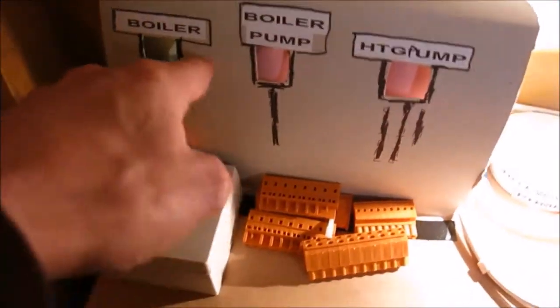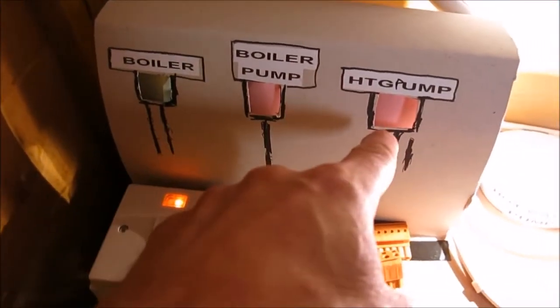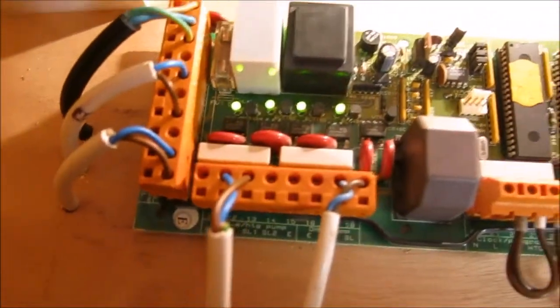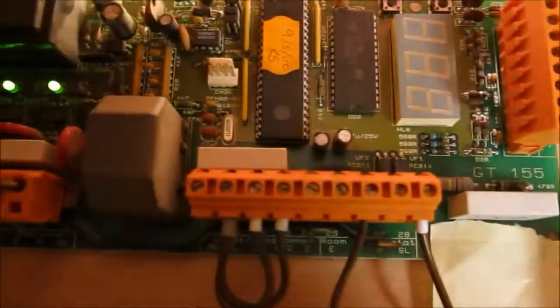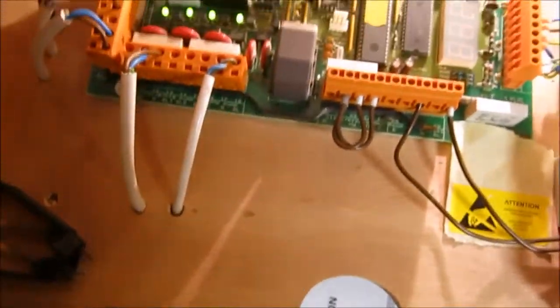I'll show you that in a minute. More importantly, if those LEDs are on, the boiler pump and central heating pump should all be on as well, and clearly they're not, because these lights aren't lit up. These lights simulate them, and that's a dead giveaway that there's a problem with it, and it should be repaired. So now I'm going to turn that off for now. I'll come back to it when it's been fixed.